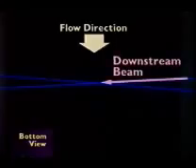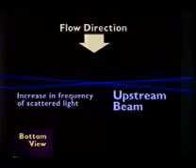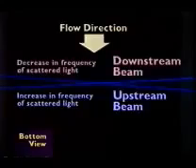What we actually do in this heterodyne system, which means we're comparing the two scattered light beams, is that we compare the upshifted frequency from one light source with the downshifted frequency from the other light source. And as the velocity increases, the shift in frequencies will increase also. So we have a very sensitive way to measure velocity.